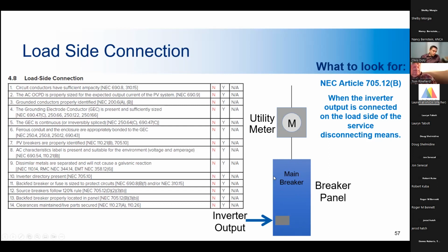If you had the solar coming in at the top of the panel and the main breakers at the top, and you are using 120 amps on a 100 amp bus bar, there would be 120 amps moving through that bus bar, and that could overload it, and like I said earlier, cause melting or cause fire hazards. So for instance, if you have 100 amp service coming into the panel, and you have a 100 amp bus rating, you can have a 20 amp backfeed breaker and it'll still be acceptable. And if your bus bar in your panel is more than 100% of the main breaker plus the backfeed breaker, then you can locate the backfeed breaker anywhere in the panel.